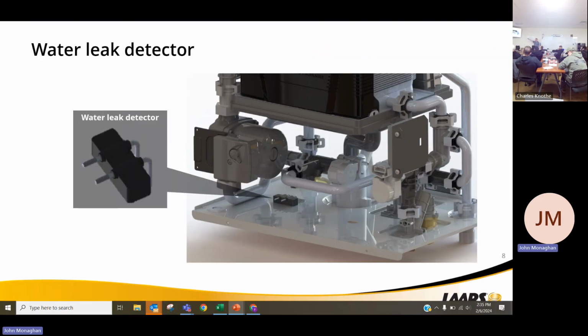I'm going to zoom in. Down at the bottom of the unit, there's a little dimpled piece where that water leak sensor is going to be. So if anything internal leaks, it's going to shut the unit down. Resettable? It is, if you dry it out, yes. Taken out and blown off, put back in. It's not single use. Or if you're working on it and you get it wet, you know what the cause of it is.